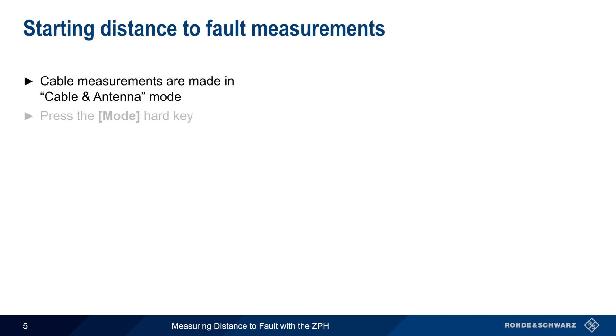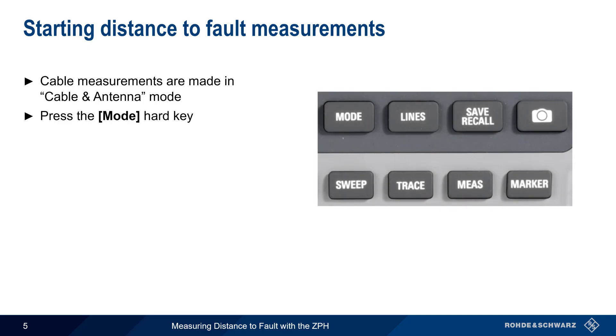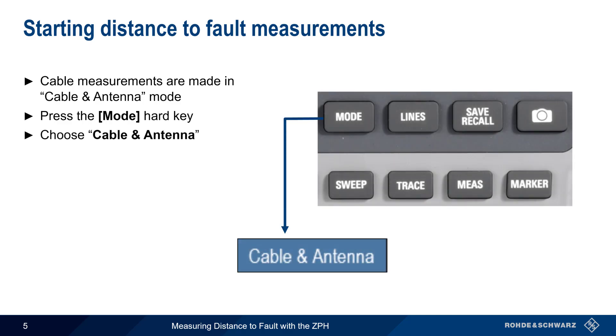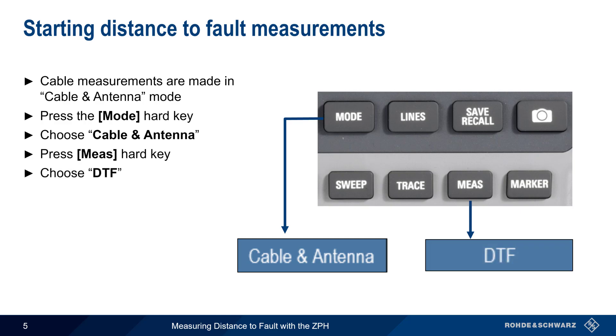On the ZPH, distance to fault measurements are made in Cable and Antenna mode. To enter this mode, press the Mode hard key on the front of the ZPH, and then choose Cable and Antenna from the list of available options. Next, press the Measure hard key, and select DTF, in order to configure and run distance to fault measurements.